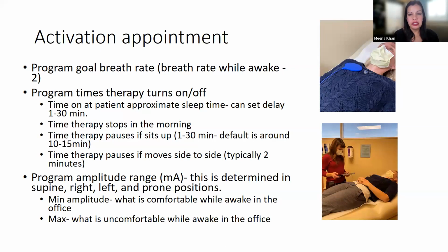So at the activation appointment, this is the telemetry cord here that you put on top of the generator, the IPG, and then this is the programmer that's used so that we can read things off the device and implant and program things into the device. The goal breath rate that we'll typically start out with is the breath rate while they're awake minus 2. So we program that into the device. We program the times therapy turns on and off. So again, the time it turns on is when the patient says they're asleep, and then you can also set a delay. So if they say, I go to bed at 11 and it takes me 15 minutes to fall asleep, you can set a delay of 15 to 30 minutes, and it will pause for that amount of time after 11 before it's going to turn on.